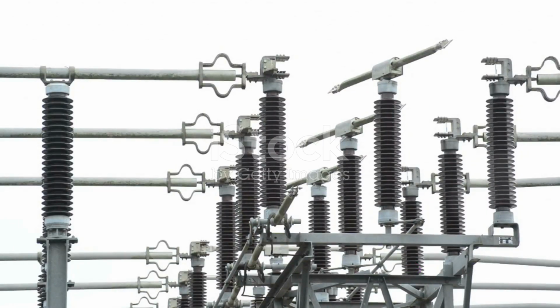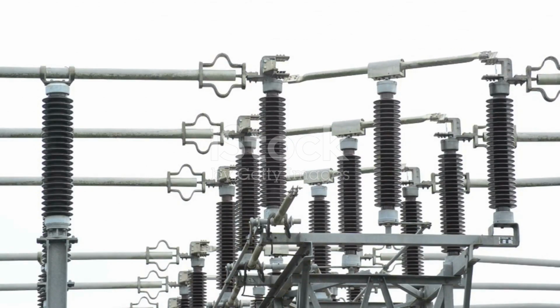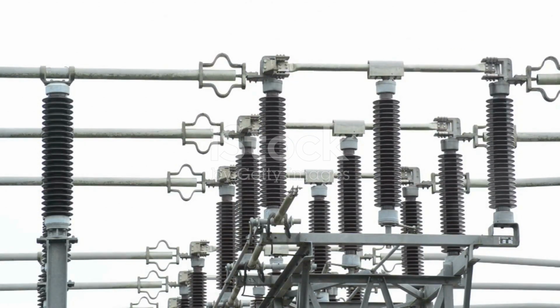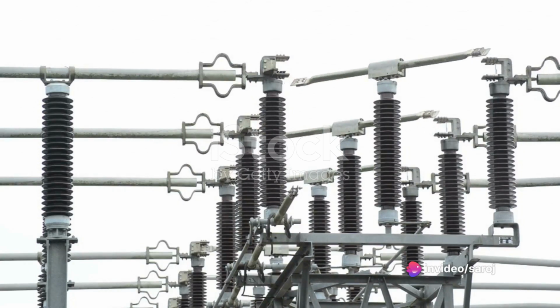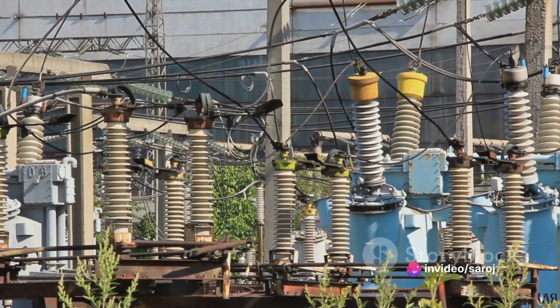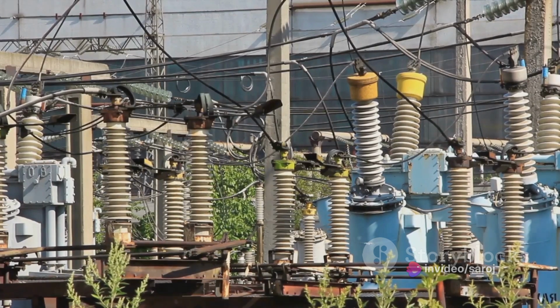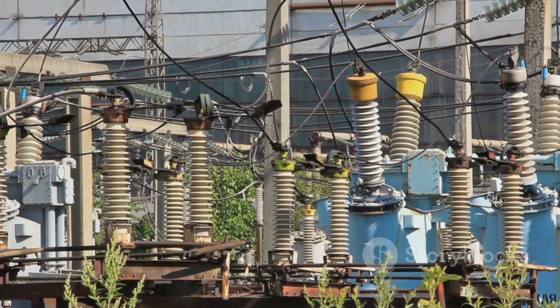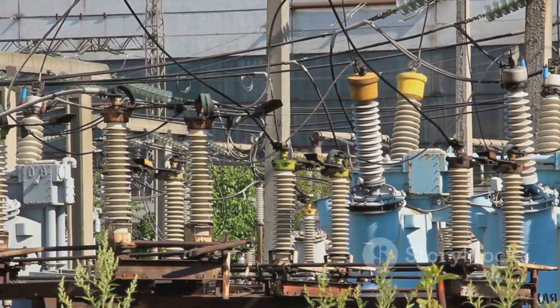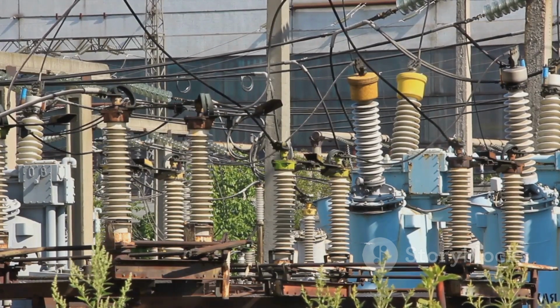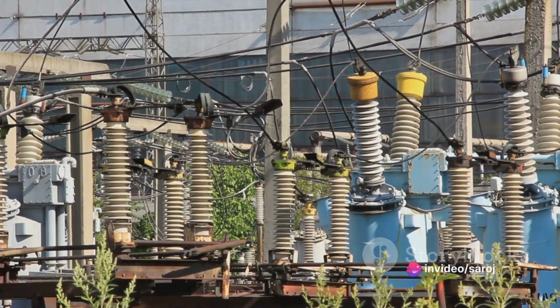First up, we have vacuum circuit breakers. These devices interrupt the electrical current by creating an electrical arc in a vacuum, an environment where the arc can't sustain itself. The arc is extinguished and the current is interrupted. Vacuum circuit breakers are compact, require little maintenance, and produce no harmful emissions, making them an attractive alternative to SF6 circuit breakers.